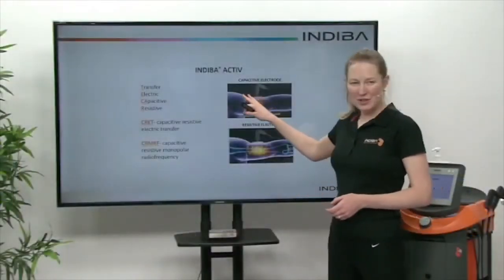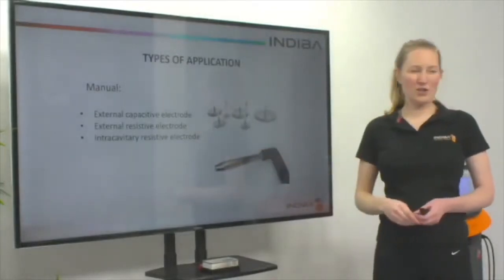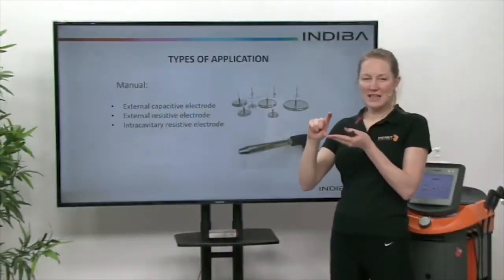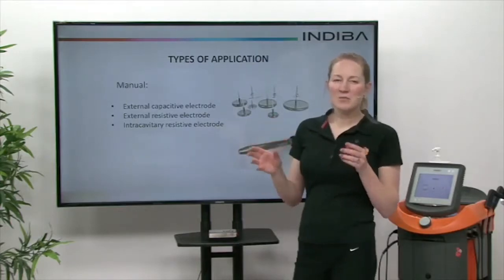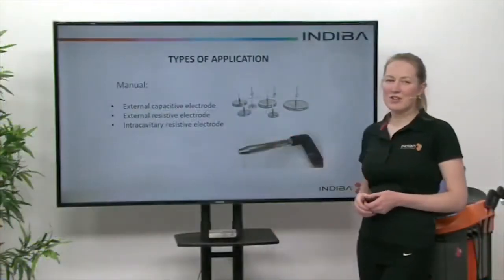So how do we apply it? We have a capacitive electrode and resistive electrodes. In different scientific terms, Indiba can be referred to as Tecar, CRET, or CRMRF. When we talk of the types of application, we always start with the external capacitive electrode. We also have the external resistive electrode, which is the bare metal ones. With the capacitive, you get a treatment effect and heat effect directly underneath the capacitive head. With the resistive electrode, that treatment heat can go directly into the body and all the way through to the return plate. You get biostimulation with both the capacitive and the resistive, but you get more heat generated deeper with the external resistive electrode. You also have an intracavitary electrode as well if you want to use it.